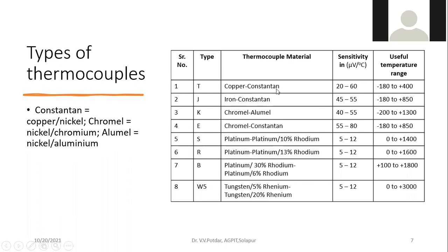So copper constantan gives me sensitivity of 20 to 60 microvolt per degree Celsius. For 1 degree Celsius input temperature difference, it will give me 20 to 60 microvolt, right? And the useful temperature range is minus 180 to plus 400 degrees Celsius. Compared to that, I have got J-type, iron constantan type, which provides me sensitivity range of 45 to 55, temperature range of minus 180 degrees Celsius to plus 850 degrees Celsius.